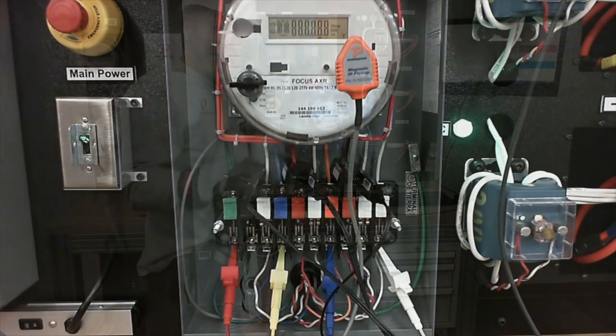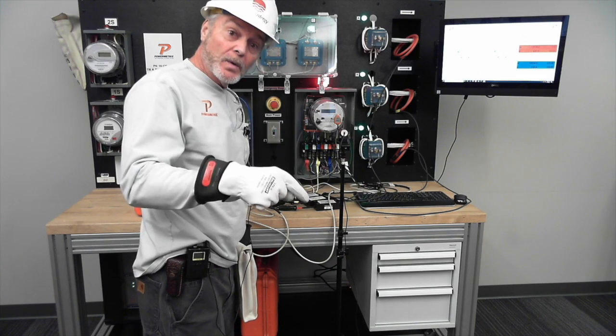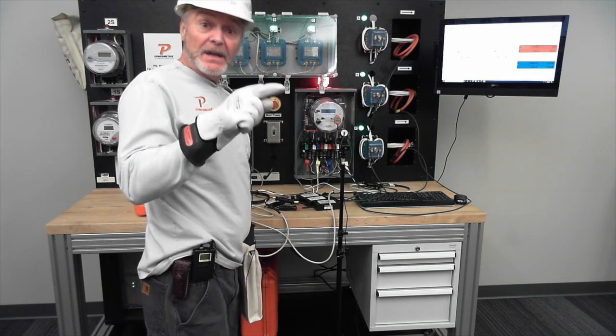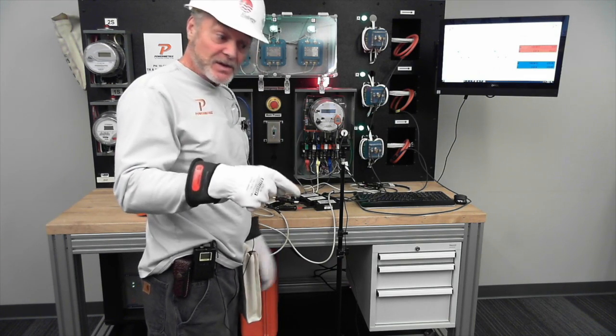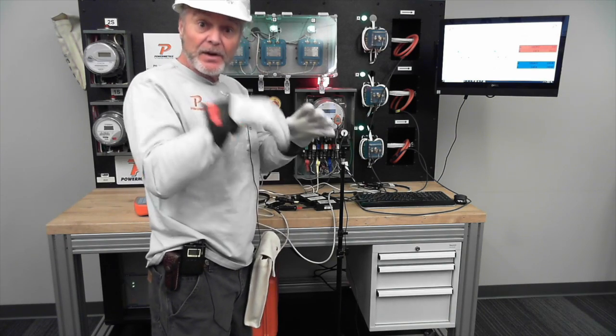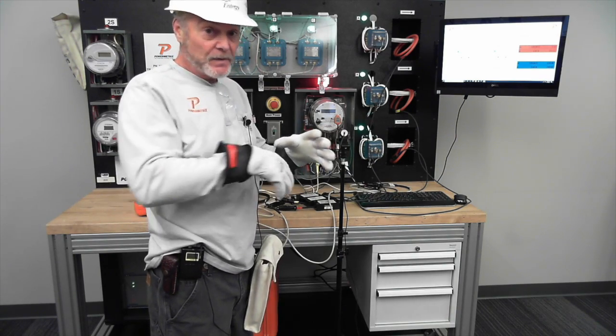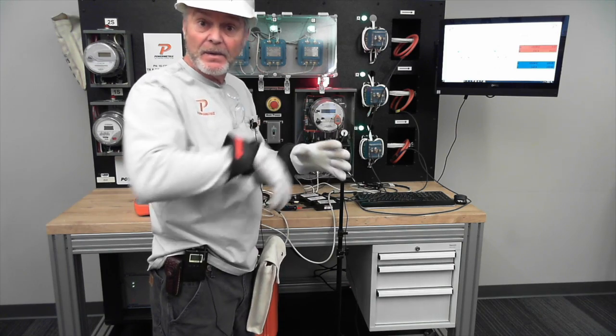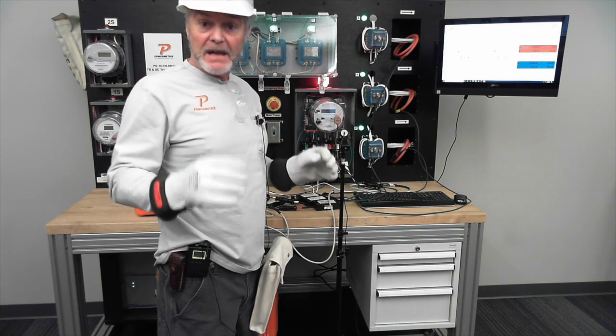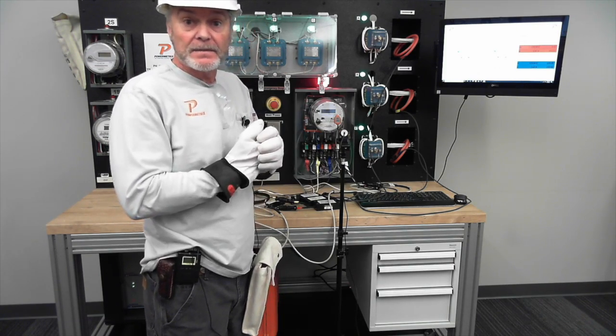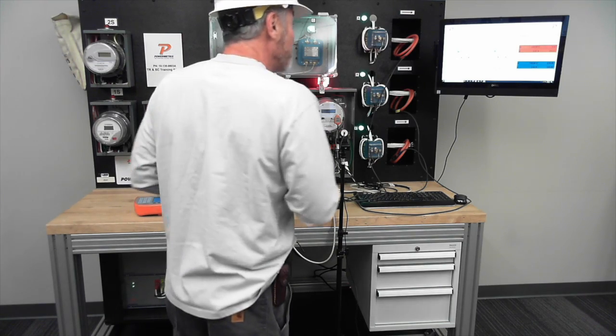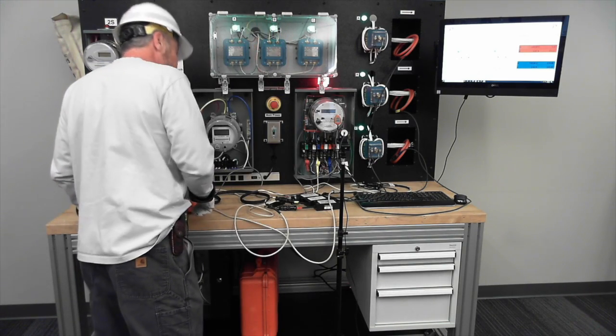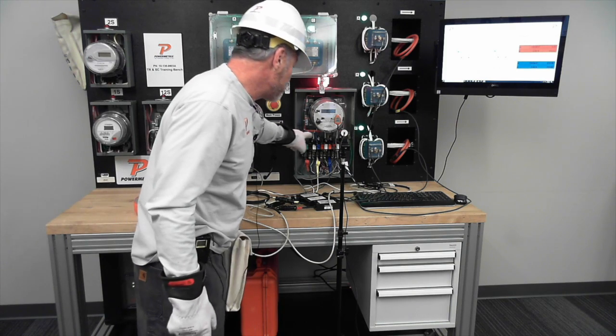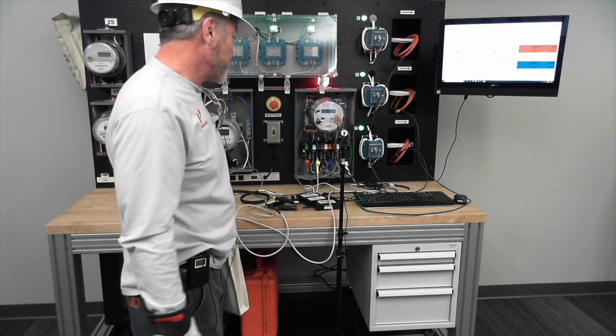Okay, but sometimes remember, with these current probes, positional is very key. Remember on our flexes, the center of that flex is the most accurate. If you move inside that flex, though, it can get worse. So positioning is definitely important when we're trying to measure our currents. So it looks like we got a pass on all those, so everything looked okay. That's using the MN114s right there.